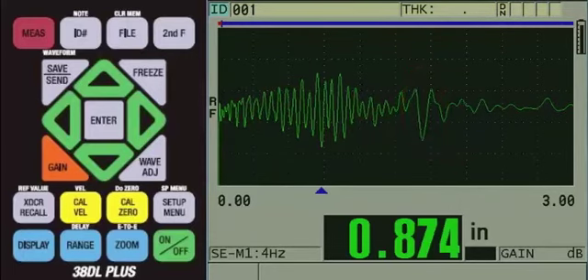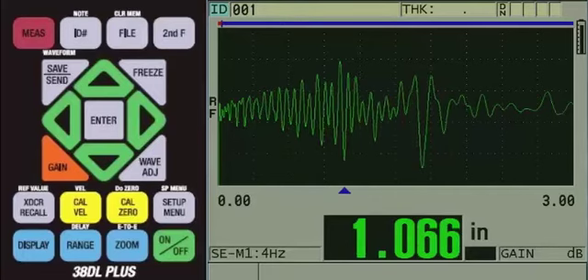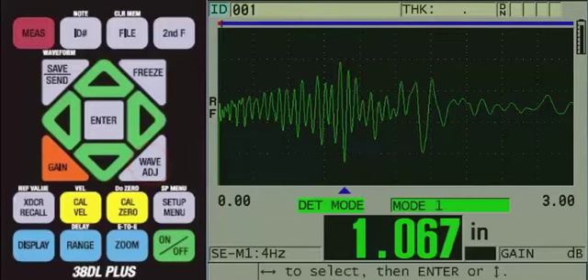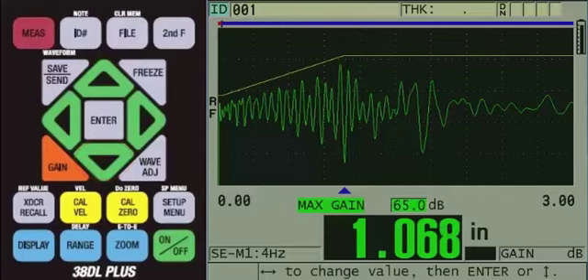In order to detect the true back wall echo, we need to make some internal adjustments to gain. To do this, press the Wave Adjust key. This will bring up the setup parameters at the bottom of the screen. Press the down arrow to the gain settings. Once you get to max gain, you will see the yellow gain line which identifies which of the 3 gain settings need adjustment. Press the down arrow to INIT gain, then use the left arrow to lower the initial gain slightly to reduce internal reflections appearing sooner in time.